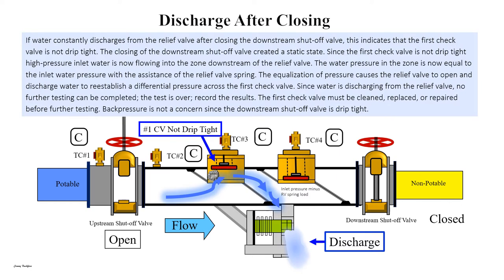Record the results. The first check valve must be cleaned, replaced, or repaired before further testing. Back pressure is not a concern since the downstream shutoff valve is drip tight.